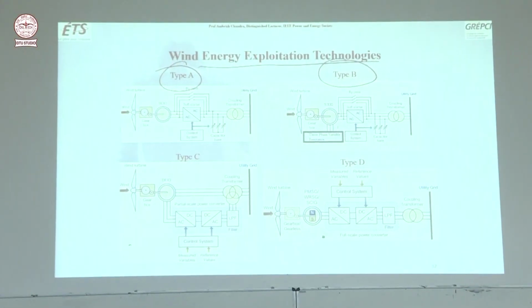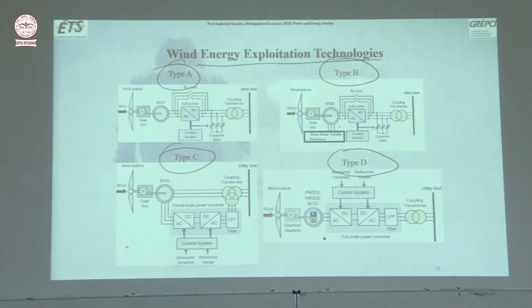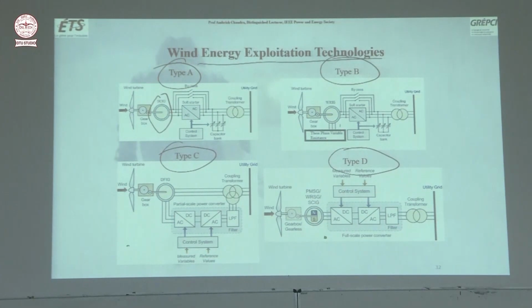So if you see the wind energy exploitation technologies, type A, type B, I think yesterday also we were discussing about the type C and type D. Type A, you see this is squirrel cage induction generator, right? And you have this wind turbine gearbox you need, and either you can connect it directly to the grid. But to have a soft start, because you already know that induction generator or motor, when you start, it takes 5 to 6 times of rated stator current. So it draws a lot of current, reactive current from the network. It may generate voltage sag condition, as we discussed the first day. So to have a soft start, you can have this, and once it starts, then you can bypass this converter. Okay, so this is type A.